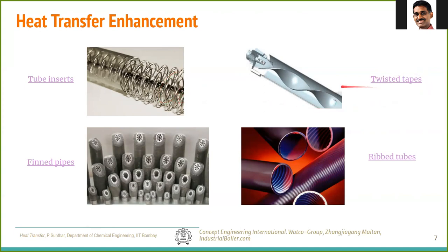The second method is the twisted tape — a ribbon twisted into a spiral inside the tube. Any fluid flowing through it goes up, down, and around the spiral. Even in laminar flow, the flow is not unidirectional: it goes up and down repeatedly, achieving very good perpendicular contact with the surface, which improves heat transfer.